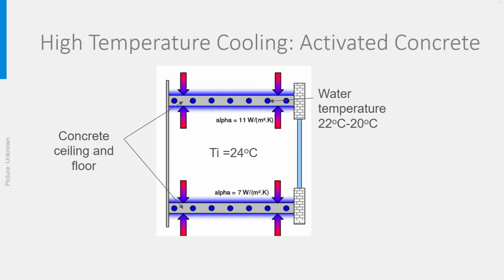An alternative to floor or ceiling cooling at high temperature is activated concrete, sometimes used in larger buildings. Instead of having cooling panels below the concrete ceiling, water pipes are now placed inside the core of the concrete, and cold water is circulated at an average temperature of 21 degrees. The supply is at 20 and the return at 22, for instance, so a very high temperature chiller can be used. The concrete construction is therefore also at 21 degrees, which feels very comfortable. This system ensures a rather constant indoor climate and is able to deliver a basic cooling load. It is, however, very slow.